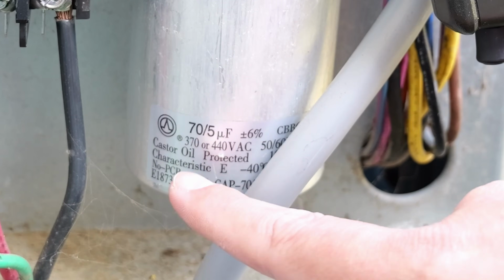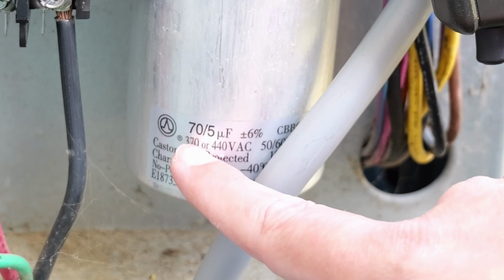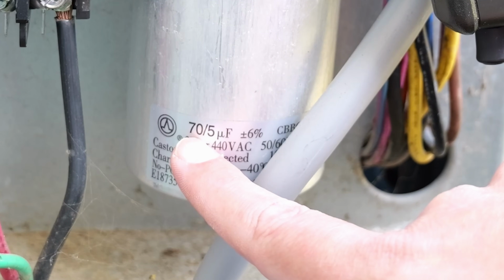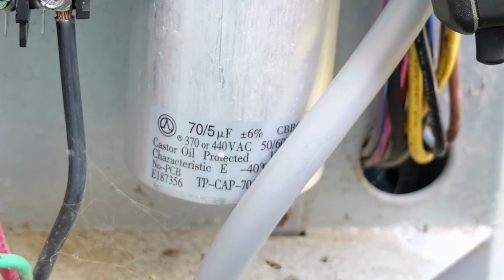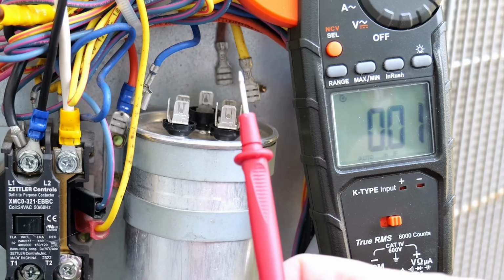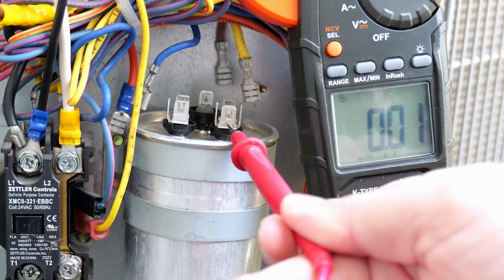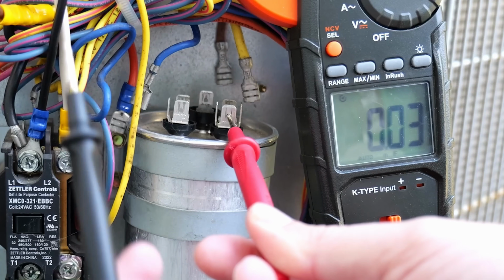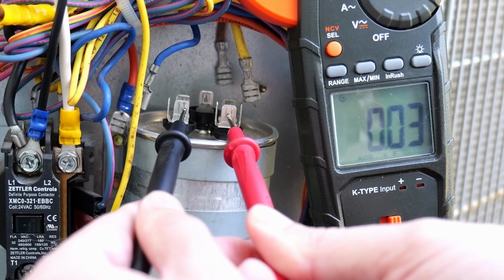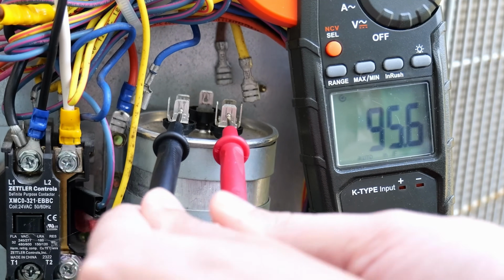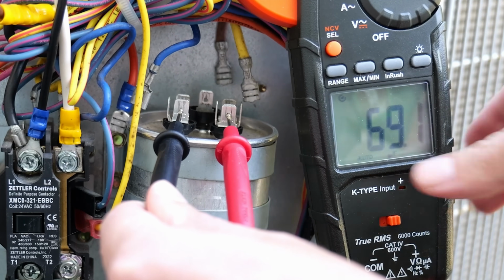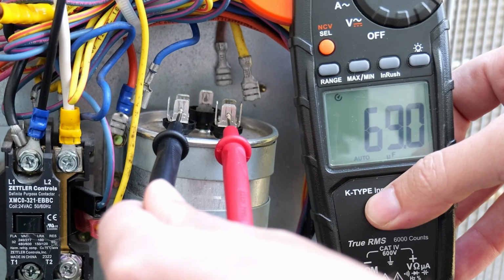All right, so my first reading, I'm going to go from the common to the herm, or hermetic, terminal. And again, we should be within 6% plus or minus of 70 microfarads. So I'm going to take my first probe and put it over here on my common terminal, like so. Take my second probe and put it over here on the herm terminal and see what reading we get. All right, so we're showing 69.1, or 69 microfarads.